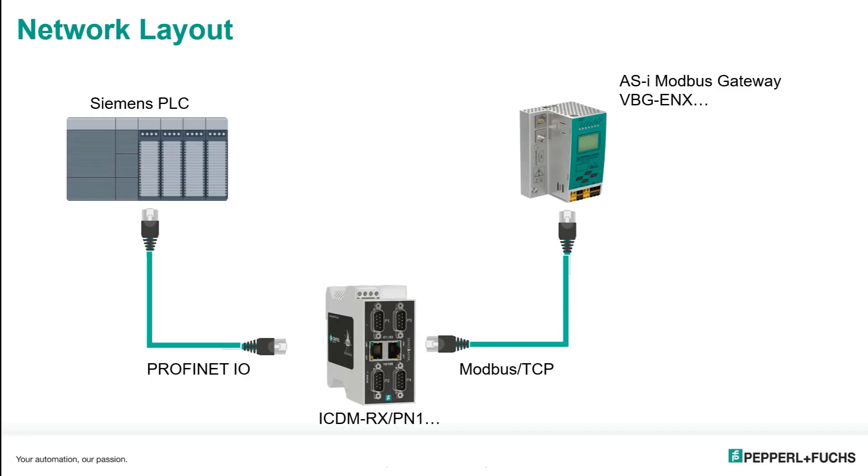So this is my basic setup. My DeviceMaster gateway you see at the bottom will convert the PROFINET I.O. protocol to and from Modbus TCP, allowing my Siemens PLC to communicate directly to my Modbus AS interface gateway. Understanding AS interface is not important. I only want to use it as a discussion point for the Modbus communication.